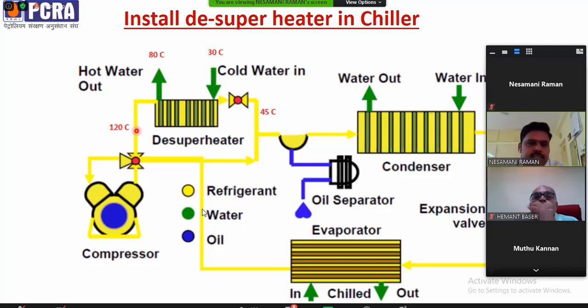So at one of the locations, the temperatures I have taken from one of the case studies. The discharge temperature was almost 120 degrees Celsius. So the desuperheater is nothing but a normal heat exchanger, where cold water is getting in at a normal 30 degrees Celsius, and they could achieve a hot water output of almost 80 degrees Celsius. The exit of the refrigerant will be only 45 degrees Celsius.